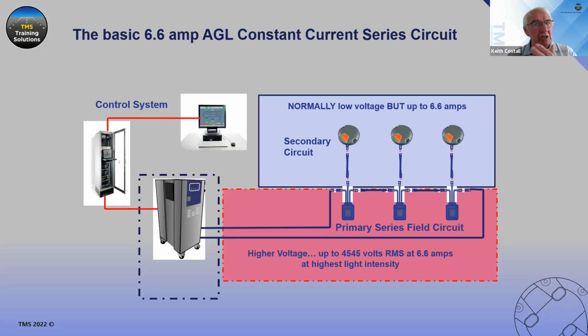We have 12 amp systems in the industry, we have 20 amp systems in the industry. So the discussions that we have on the 6.6 amps are equally applicable to the 12 amp and the 20 amp systems. The primary circuit is where we connect from the power unit, which is in the substation, switch room, vault, whatever you want to call the building, the constant current regulator. And there we have voltages in a 6.6 amp system up to 4,545 volts RMS, and much higher before a CCR will trip out in a fault condition.